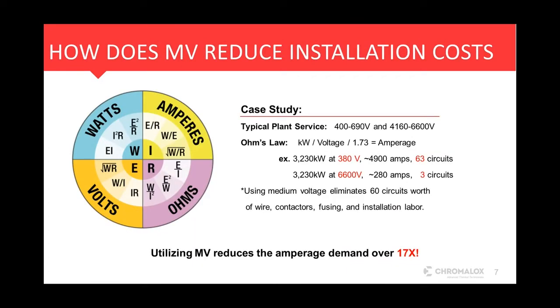So using another benchmark, looking at an even larger system, a 3.2 megawatt system at 380 volts pulls almost 4,900 amps. In conventional circuit splits, that's about 63 circuits. Again, an equivalent system at 6,600 volts pulls nearly 280 amps. Conventionally speaking, you can do that in about 3 circuits. So that's a reduction of about 60 circuits of not only the wires, the contactors, and fusing from a mechanical standpoint, but also the time it takes to install those systems.